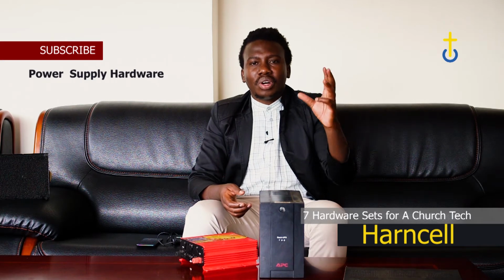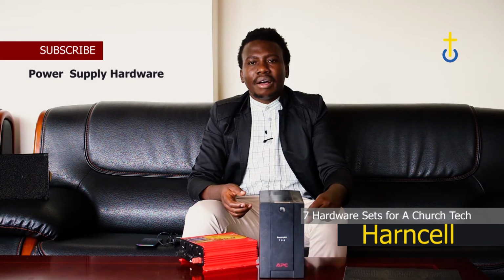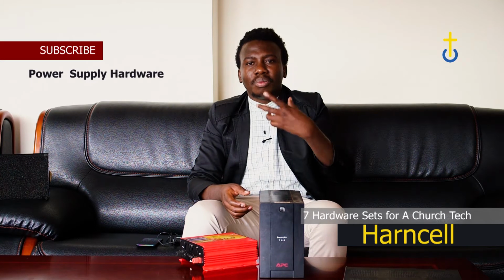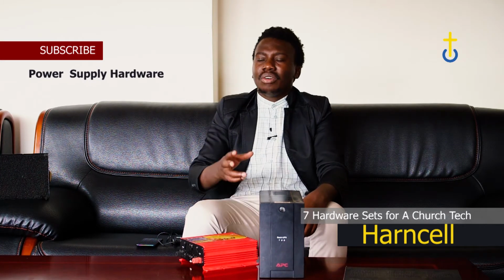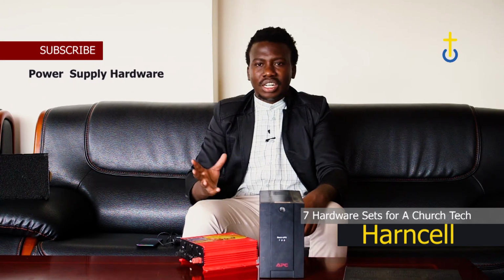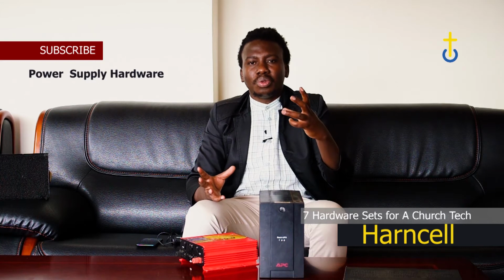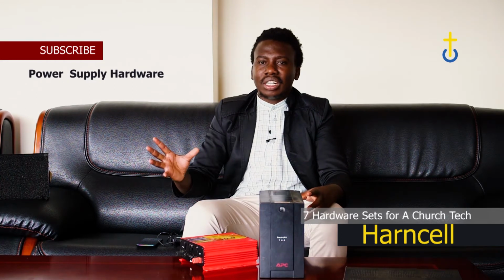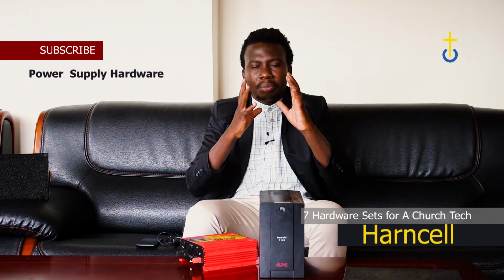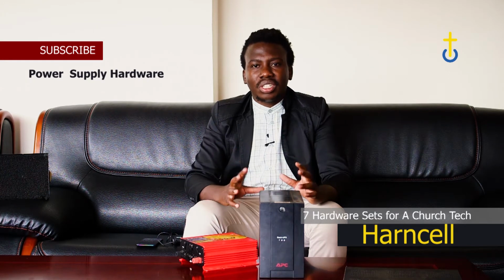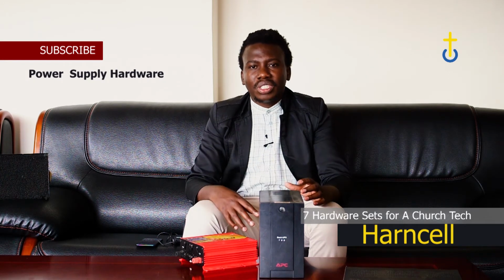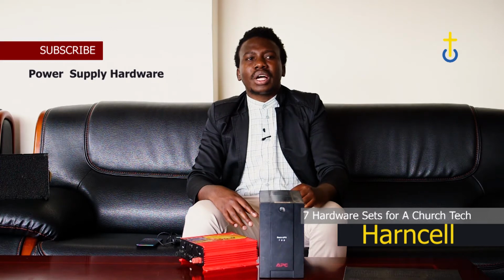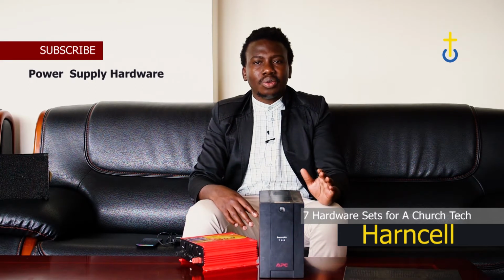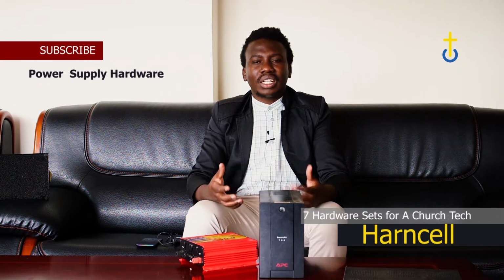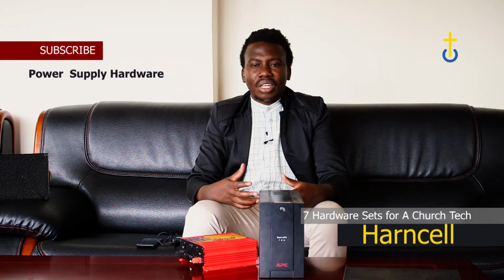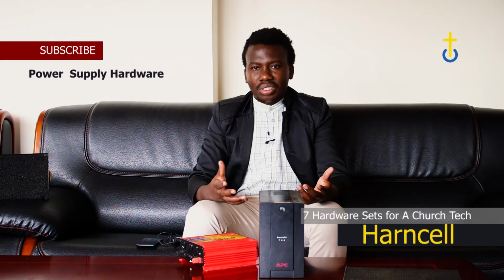For example, if you have the normal power supply from the power generating company, and you also have a generator, before you install a generator, you need to get the changeover switch. The purpose of the changeover switch is simply to cut out one supply, so that you don't have two supplies coming in at the same time, which might overload your system.